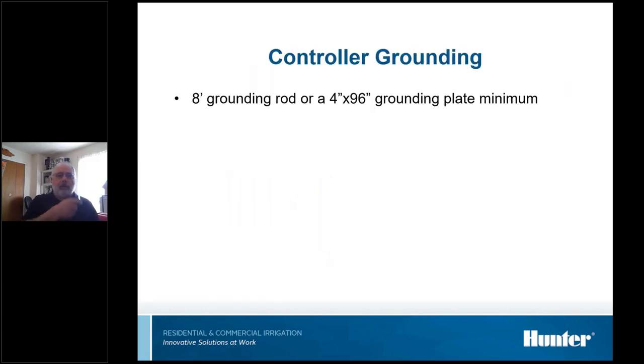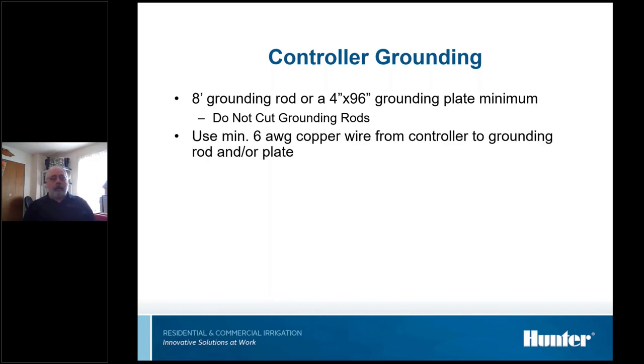As far as grounding controllers, we're either going to use a rod or a plate, one or the other, or both. A lot of times we use both on a controller. If you are using rods, don't ever cut a ground rod. If you can't pound it in all the way, you either need to go to a plate or attempt with another rod in another location. If they're not in all the way, they might as well not be there at all. Then we use a 6-gauge wire minimum. This needs to be solid core wire going between the controller and the grounding rod or plate. If it's a plate, it'll come with the wire already attached to it for you. On a rod, we'll have to add our own. And we just use acorn nuts to attach to the ground rods.